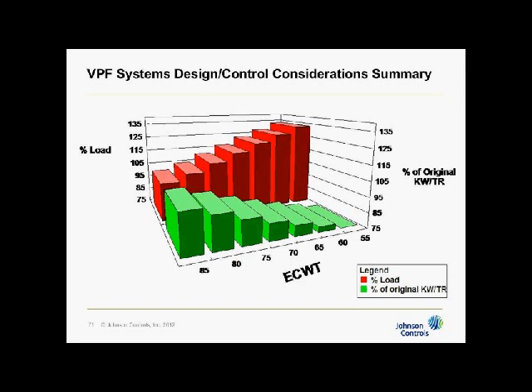And here is a graph of that. Over here on the right is percent of the original kilowatt per ton, and on the left is percent load. As you can see, at 85 degrees entering condenser water temperature, the chiller is at 100% load. As I reduce the entering condenser water temperature, you can see the kW per ton decreases. But as noted before, with all centrifugal chillers, under those conditions, you can also achieve more capacity than design at reduced tower temperatures, and at the same time lower kW per ton.